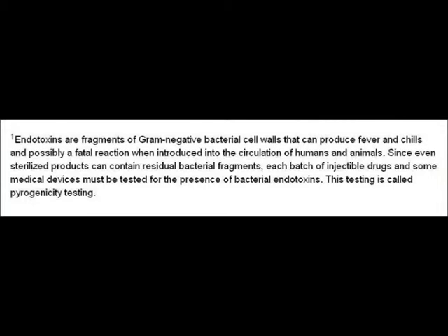It reads, endotoxins are fragments of gram-negative bacterial cell walls that can produce fever and chills, and possibly a fatal reaction when introduced into the circulation of humans and animals. Since even sterilized products can contain residual bacterial fragments, each batch of injectable drugs and some medical devices must be tested for the presence of bacterial endotoxins. This testing is called pyrogenicity testing.